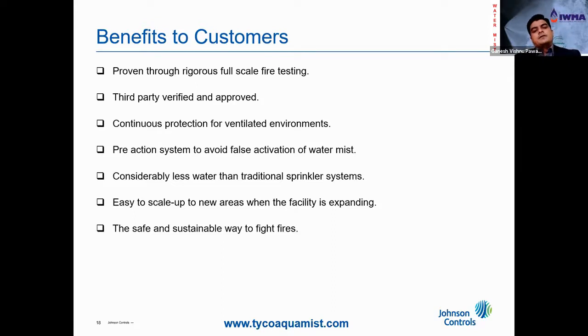When we compare the water requirement, water mist utilizes a significantly lesser amount of water with respect to a traditional sprinkler system. It also gives us the flexibility to scale up to new areas when the facility is expanding. We just need to consider an additional set of sprinkler heads and the necessary valves, because the same water mist skid will be able to take care of the new facilities. And since we are using water as the only suppression agent, it is the safest and most sustainable way to fight fires.